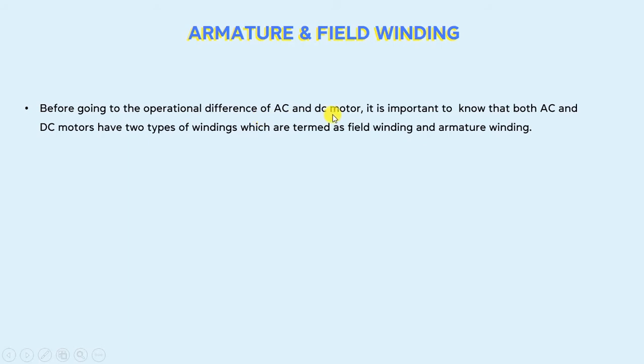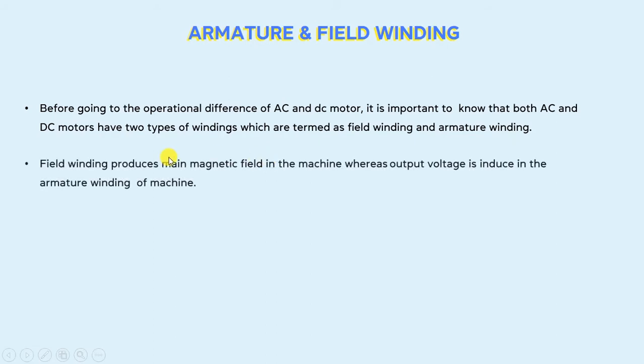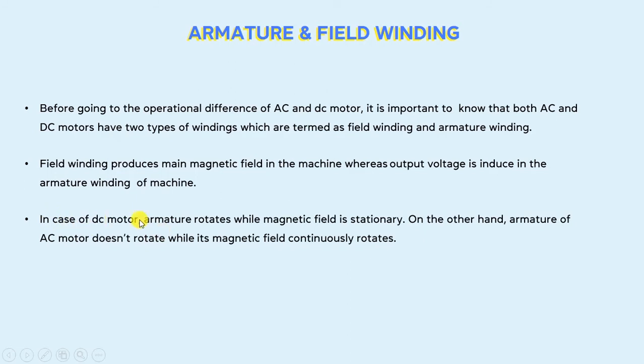Before going to the operational difference of AC and DC motors, it is important to know that both AC and DC motors have two types of winding: field winding and armature winding. Field winding produces the main magnetic field in the machine, whereas output voltage is induced in the armature of the machine. In the case of a DC motor, the armature rotates while the magnetic field is stationary. On the other hand, in an AC motor, the armature does not rotate while its magnetic field continuously rotates.